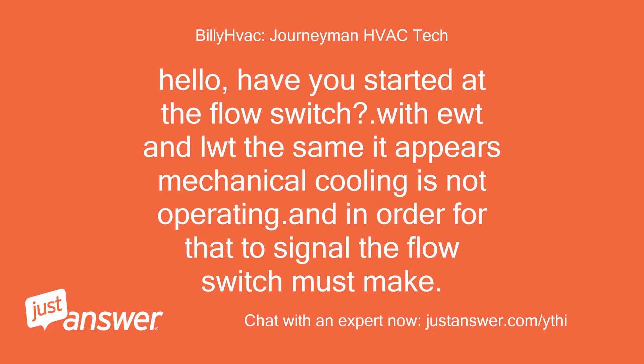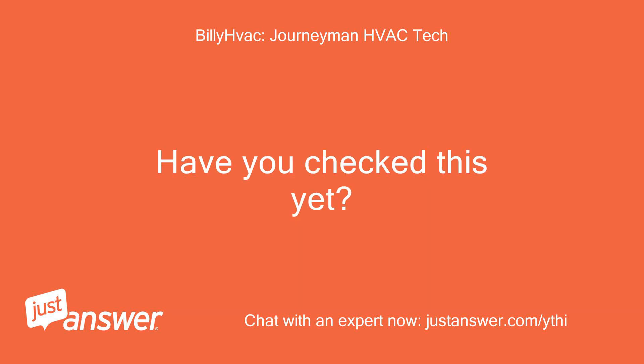Hello. Have you started at the flow switch? With EWT and LWT the same, it appears mechanical cooling is not operating. In order for that to signal, the flow switch must make. Have you checked this yet?